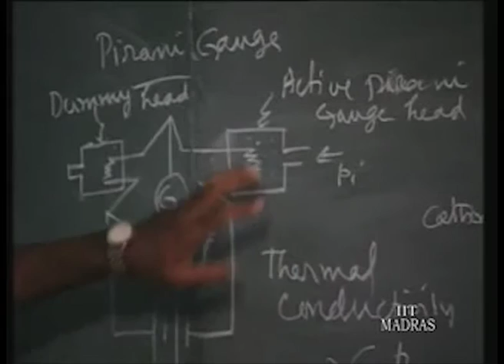So this you have to calibrate. For calibration purpose, you fill this volume with the gas at say 1 torr, and the adjacent arm is a similar unit, but a dummy head. It is completely evacuated and sealed. You can have a similar resistance, but it is easy to have the dummy head and fix it as the adjacent arm. Now fill this volume with gas at 1 torr. That means you will have enough molecules to take the maximum amount of heat from the filament to the casing. Then the temperature will be low, and the resistance also will be low accordingly.